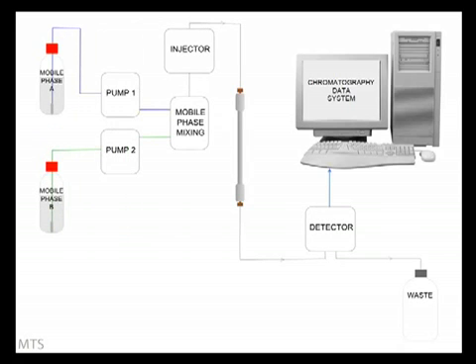Or the mixing may be performed after the mobile phase flows through the pump, in which case it is under pressure and two pumps will be required. Systems which use high pressure mixing are often referred to as binary systems since two pumps are needed.